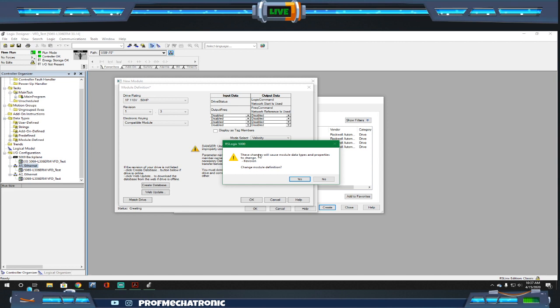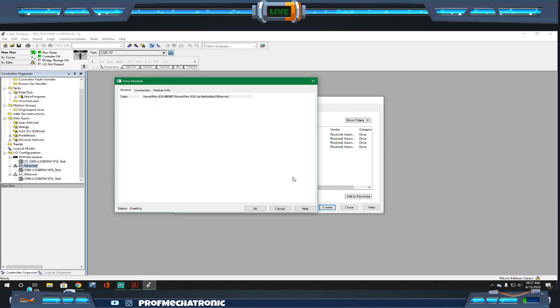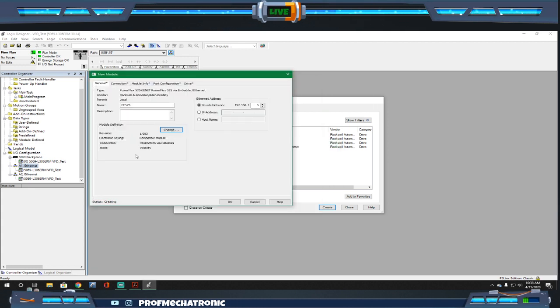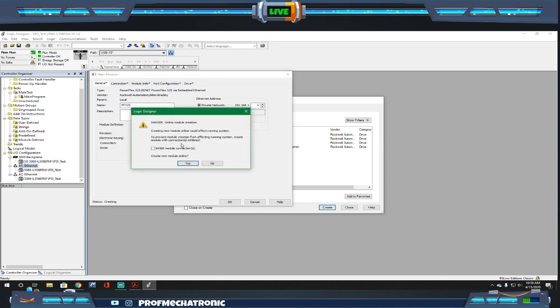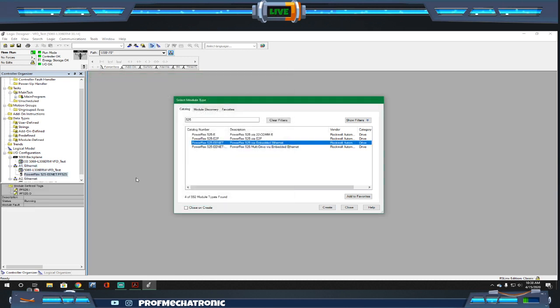From there, you hit OK. It's going to give you a warning saying that it's going to change the data types and the properties. Are you sure you want to do that? We're going to hit yes. And then we're going to verify that everything here is set up the way we want it to be, and we're going to hit OK. It's going to say, are you sure you want to create this online? If you create this live and online, you may have some issues. So are you sure you want to do that? Normally in industry, we wouldn't want to create these online. You don't want something to arbitrarily move or be adjusted. So you would want to do this as an offline process, add all these devices, and then download them. But this is just a simple way to add this module online into our current system.